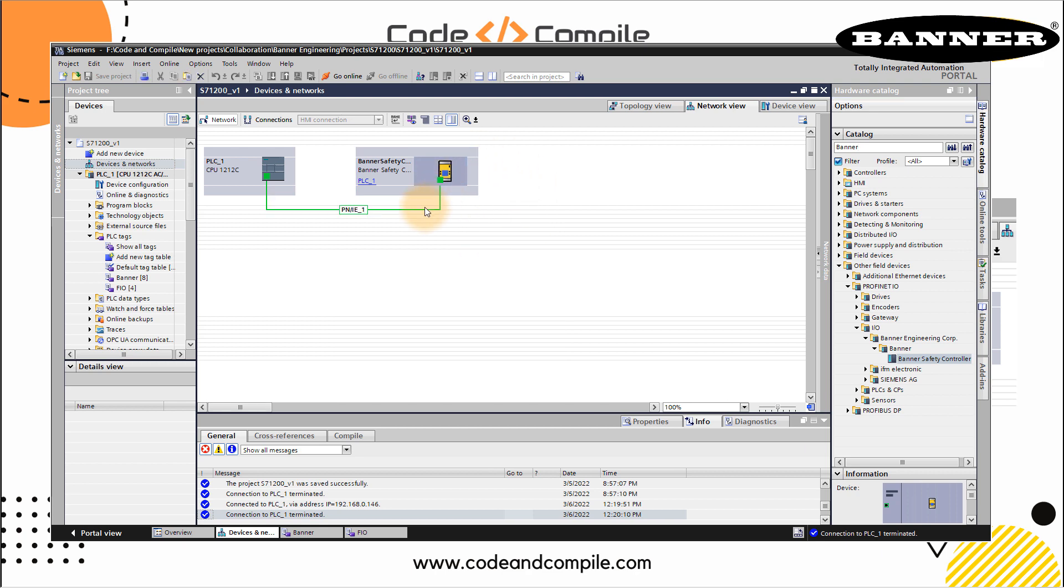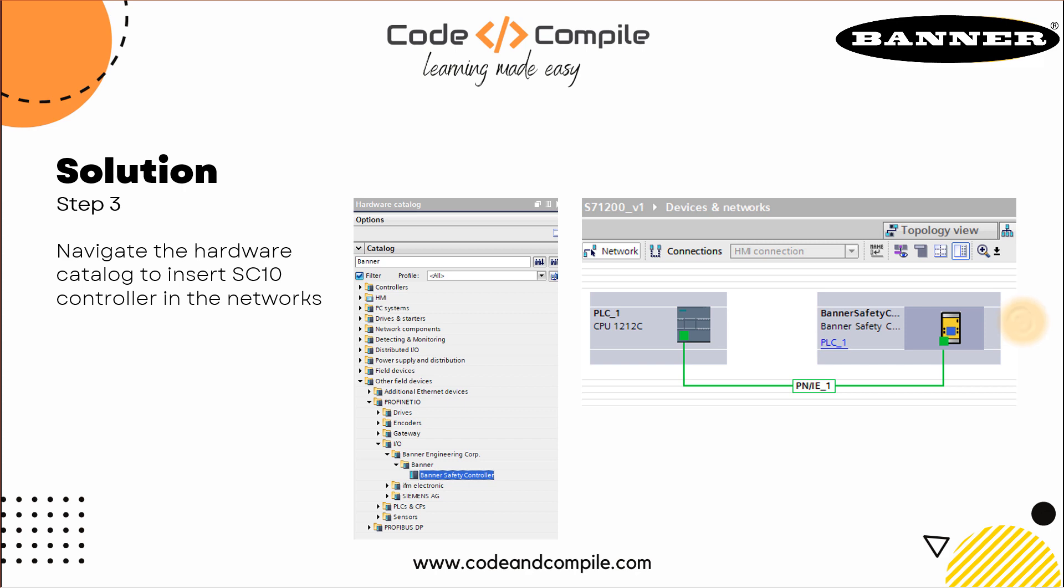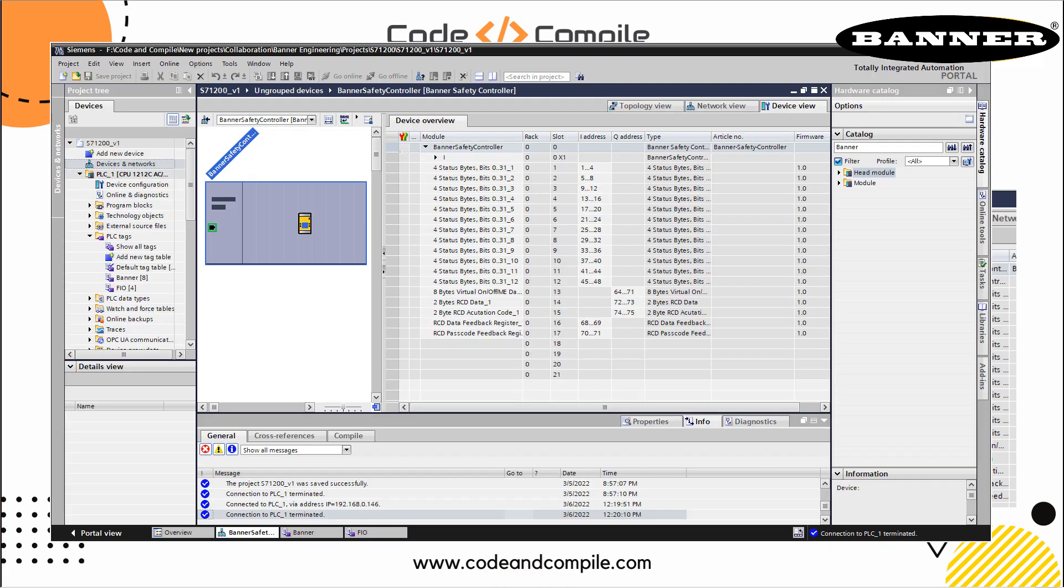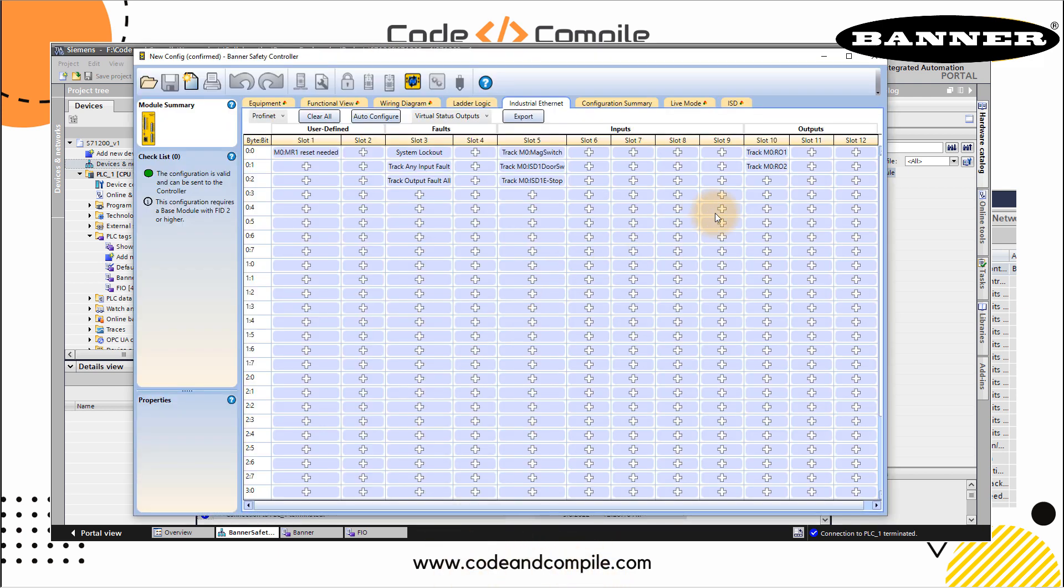Once this is connected to the PLC, you can go inside by double click. Then you will see all the addresses of this SC10 controller. This is also explained in the next step. Here is all my I/Os which are already configured via this GSD file. All I have to do is I have to read this I/Os in a PLC tag in my Siemens PLC. For example, here you will see four status bytes. Here you can see slot one.